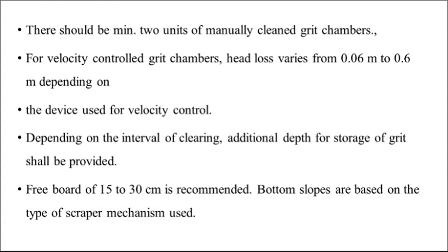Depending upon the interval of cleaning, additional depth for storage of grit shall be provided at the bottom. Freeboard of about 15 cm to 30 cm is recommended. Bottom slopes are based upon the type of scraper mechanism used for removal of the grit.